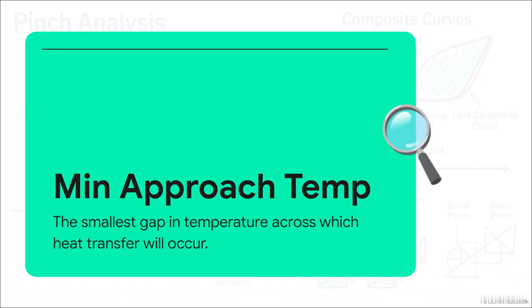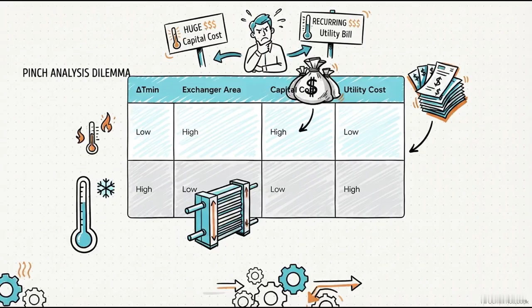If you choose a very low delta T min, you decrease your need for outside heating and cooling, which sounds great, right? But because that temperature gap is so tiny, you need a massive, highly expensive heat exchanger to actually do the work — a huge upfront capital cost. On the flip side, if you allow a high temperature gap, sure, you can buy a small, cheap heat exchanger up front, but you'll be paying a massive ongoing daily utility bill to make up the energy difference.